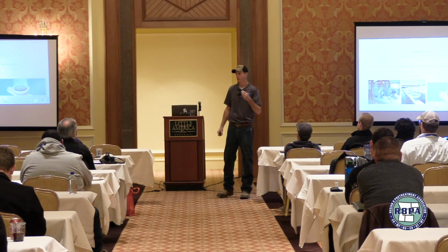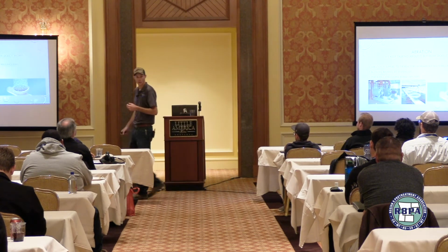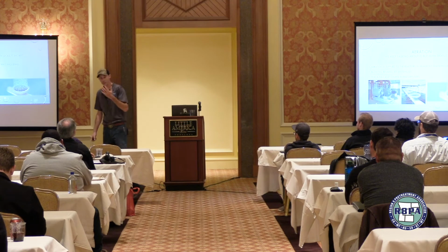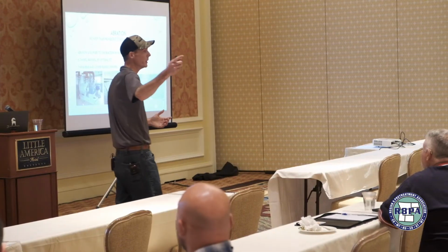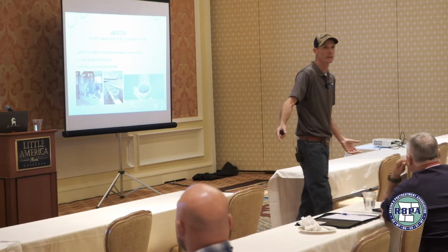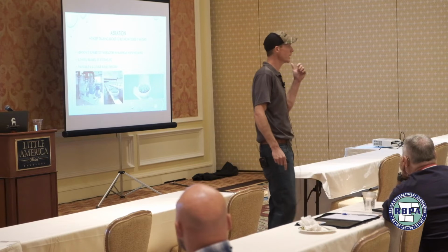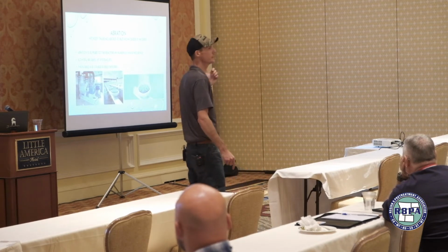Why? It costs money. How much is a high-speed turbo blower? We're talking $1 million, $1.5 million per blower. So if you put in a bunch of blowers that you don't need, they made a bunch of money, and you can't shut your air off. Who's getting hosed? You can't denitrify fully. Can you meet Reg 85, Reg 31 in Colorado when you can't denitrify? Not a chance in hell.